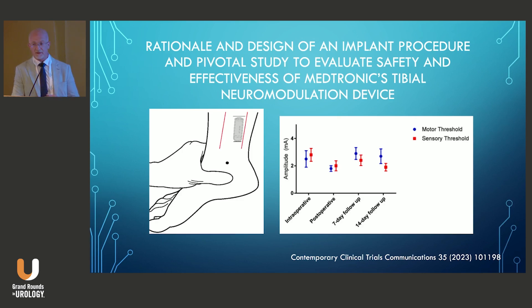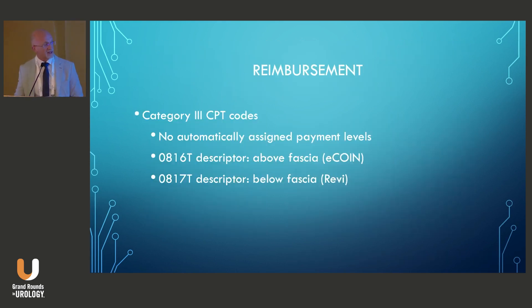From the Titan 1 findings, they designed the Titan 2 trial, which was the actual clinical trial. Patients would be activated within 24 hours of implant, receive stimulation every other day for 30 minutes, and the primary endpoint would be the percentage of patients with greater than 50% reduction in urge incontinence episodes at six months. We're waiting for the final clinical results of that study.